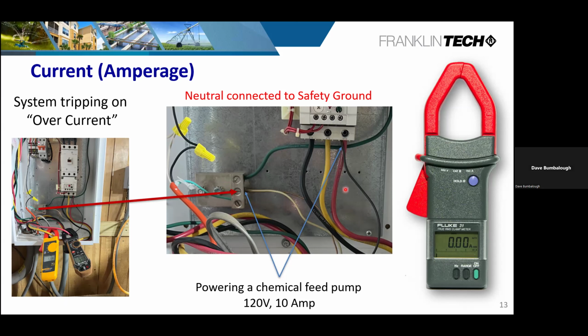Okay, and then the other factor is this power supply going to that chemical feed pump. On the side of some of these contactors, there's a secondary circuit over here on the side. It's kind of hard to see it in this picture, but if I was to blow that up, you would see there's basically another circuit there that you could use. As that contactor closes, it closes a set of points to run a chemical feed pump. If you're pulling off here, you're doing 2 things. You're adding amperage, in this case 10 amps, to this one line. You're going to throw this device into either an unbalanced situation or an overload situation, and so it's going to trip. At this point, when we took this off of there, the system ran flawlessly. Okay, so the idea here is to trace down to see where this dilemma is, and it happens often.